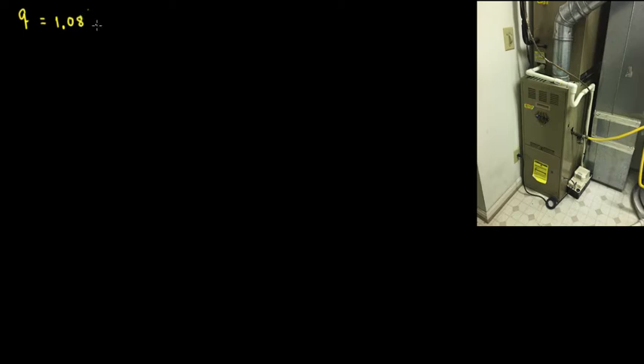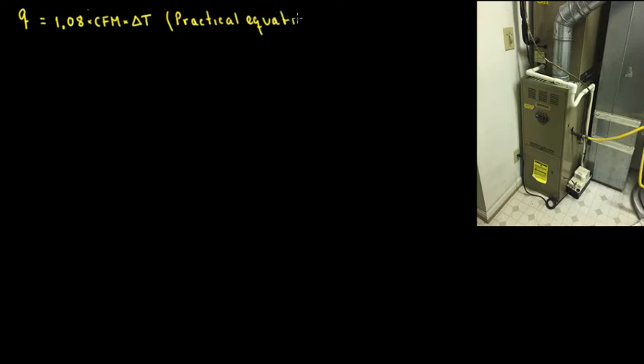So let's start writing the equation. The sensible heat equation is Q = 1.08 times CFM times delta T. This is a very practical equation — what we use in the field. Sometimes other books or references say 1.1 times CFM times delta T.